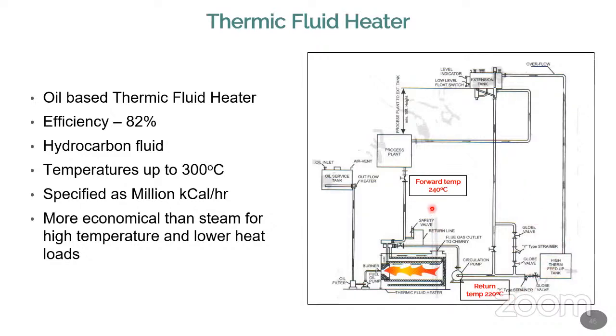So it flows out at 240° and returns at 220°. Only 20° is the drop in the entire system, which means it is used for the process, not lost. Sometimes there is loss also, but it is a very small quantity. The fuel is oil, and it keeps on circulating in this way. The heat is used to heat the oil, you use the heated oil for the process, and the process gets the heat from the system. Instead of steam, this is very good. From the fuel point of view, there is no need for a huge plant or a huge system for storing the fuel. With a wood-based boiler, you can see something like at least half an acre of area is required to store the wood.